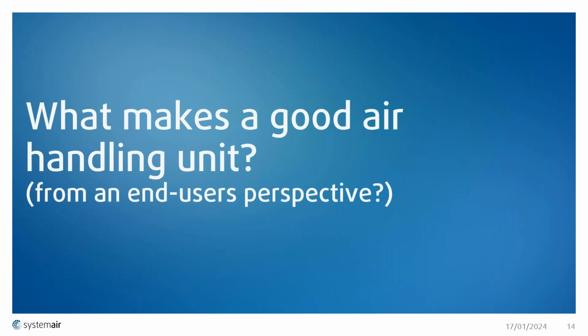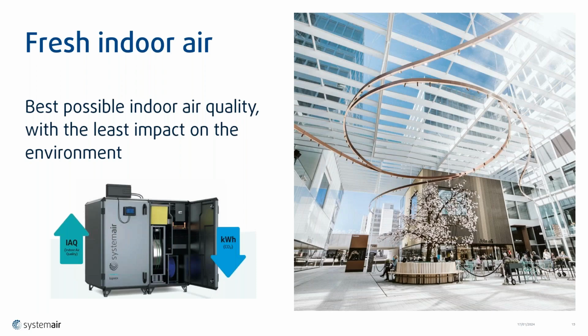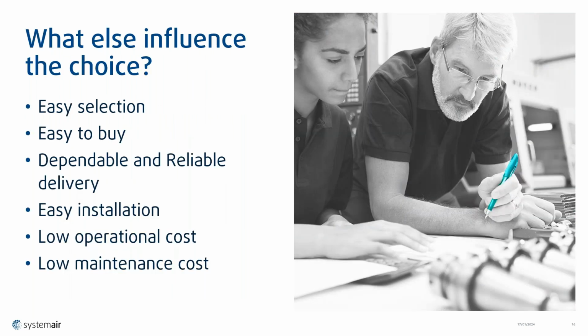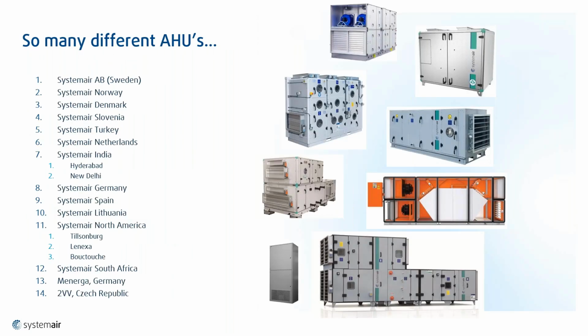It's going to be everything from dollar per CFM to indoor air quality. So from our perspective, the best way that we could define what makes a good air handling unit is the best possible indoor air quality with the lowest impact. So the most air using the least amount of energy. That's what we try to do. There's obviously other factors that influence that choice as well. You have to have an easy selection, has to be easy to buy, dependable, reliable, and then very important is low operational costs and low maintenance costs.